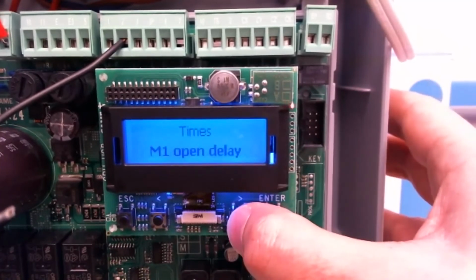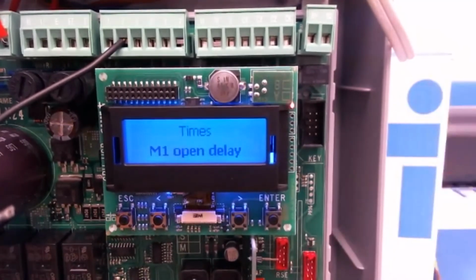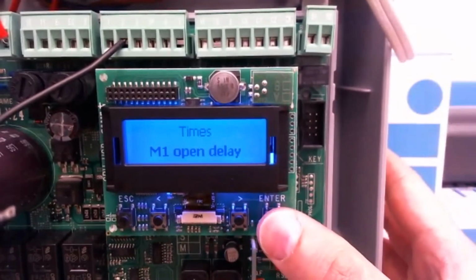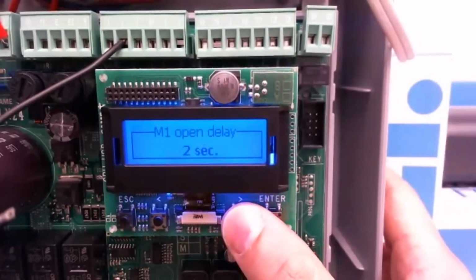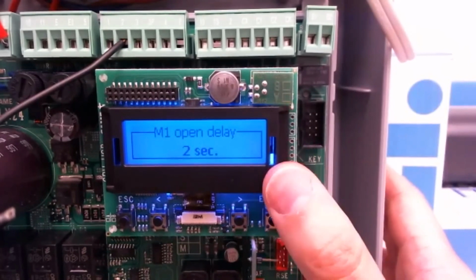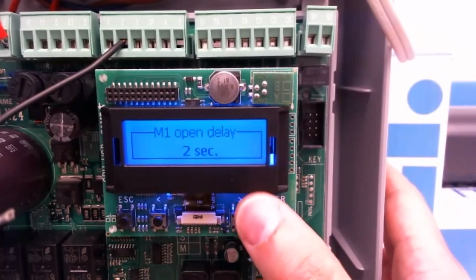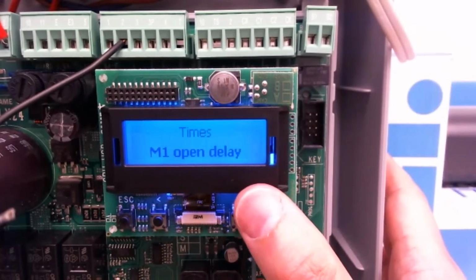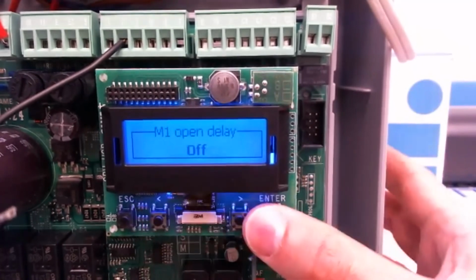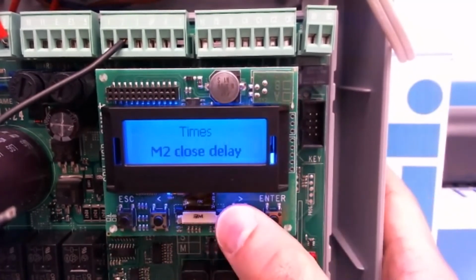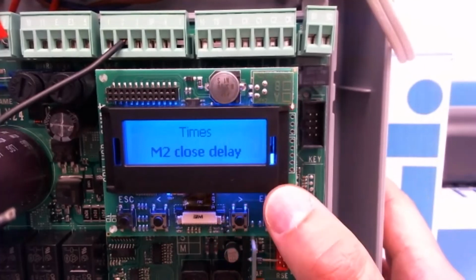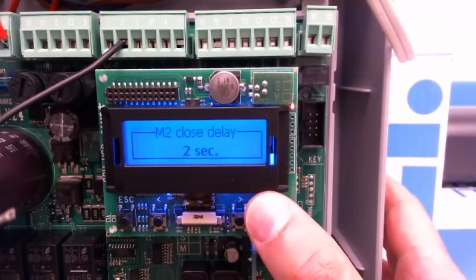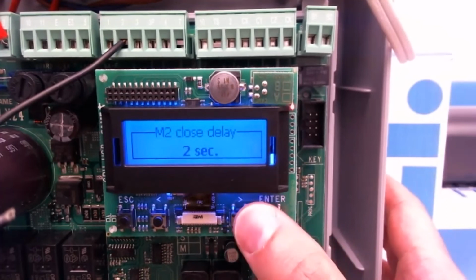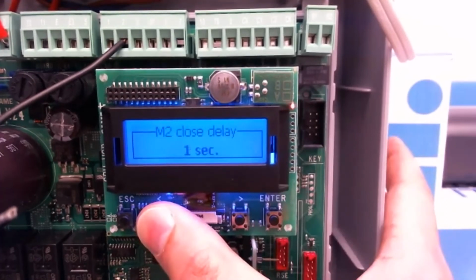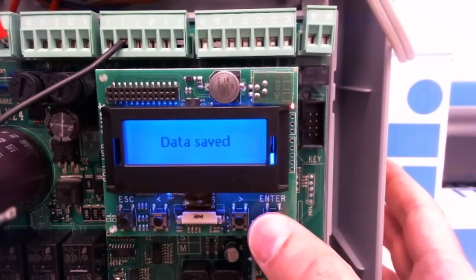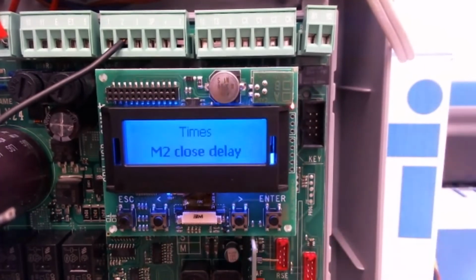Now you see the option M1 open delay - that's the delay for motor 1 to open. Right now it's off, but by default it's 2, since I've been playing with this board. By default it's 2, but if you don't want that delay, set it to off and press enter. Same for M2 close delay - that's the delay for M2 to close. By default it's 2, but if you don't want it because they don't overlap, turn it off, and both will open and close at the same time.